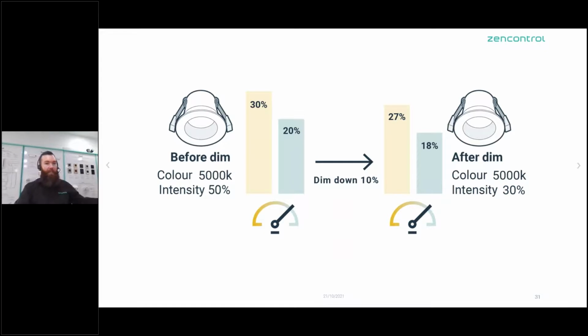Previously, if you actually had two different types of strip in your light, one unit was 5 and 2 and one unit was 6 and 3, you'd actually have to send different combinations of commands to both of those devices to be able to achieve that type of mixing. The other one that I haven't mentioned here is that it used twice the number of addresses. As we all know, the DALI network supports 64 devices on each line. And if you're using color temperature control, you lost half of them straight away because every light used 2 addresses, which meant a maximum of 32 devices.